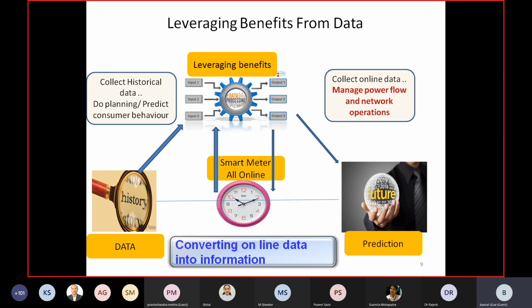Now to manage faults, outages, and damages due to overloading etc., you have to have online data. You cannot do any analysis or prevent them just with historical data. Suppose a historical data, one month old, shows there was a hotspot at a particular location - after one month you can't do anything. By the time you reach there, that hotspot has already converted into a fault. But if it is online data, you can do a lot many things - you can prevent a fault, prevent damage, maybe prevent an accident.